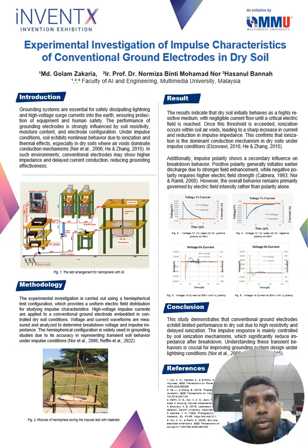So we need to remove the heat, because if we inject 5 kV, the soil will be heated. If we then inject 10 kV instantly, since the soil already has heat, we can get current immediately just because of this previous heat. So we need to remove the heat from the previous injection. That's why we need to give rest to the soil. So we maintain 5 minutes.